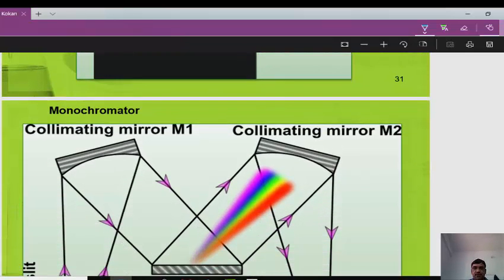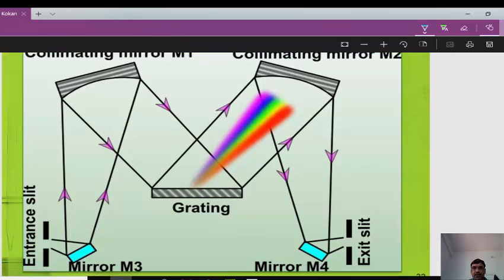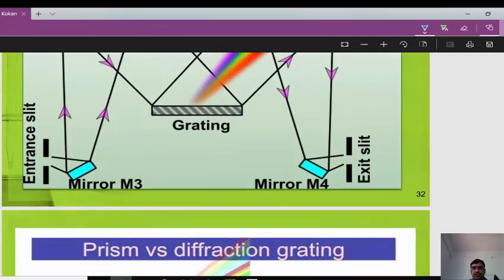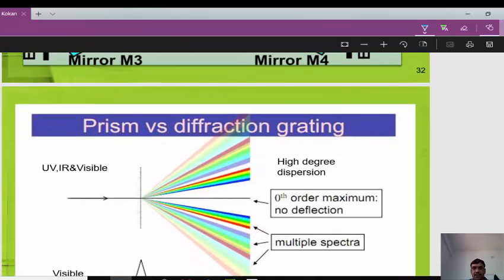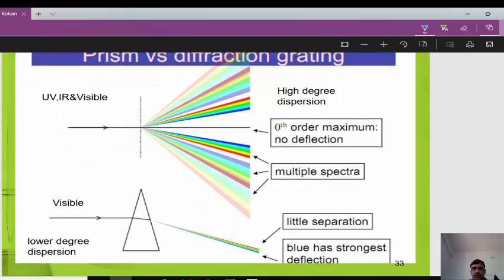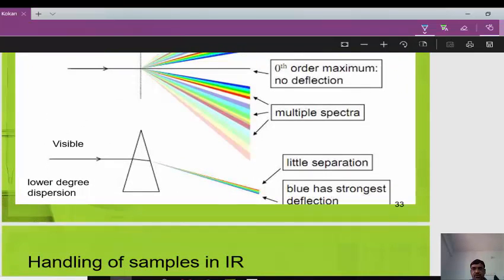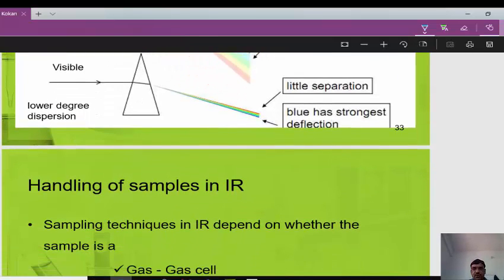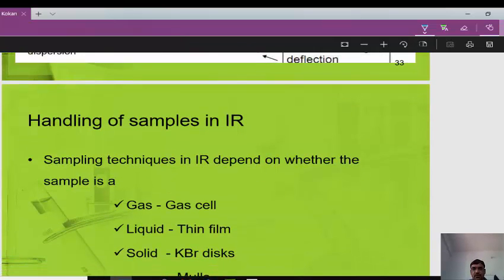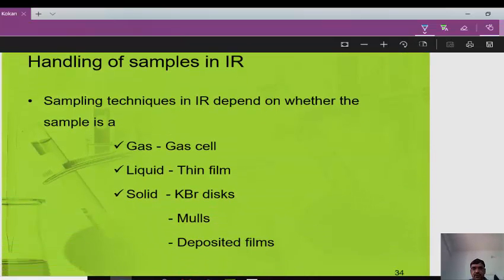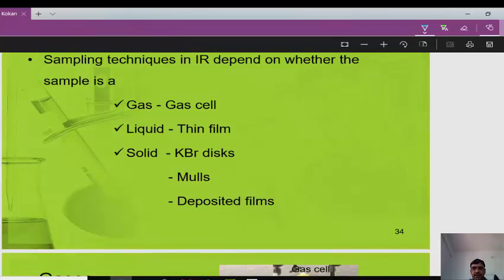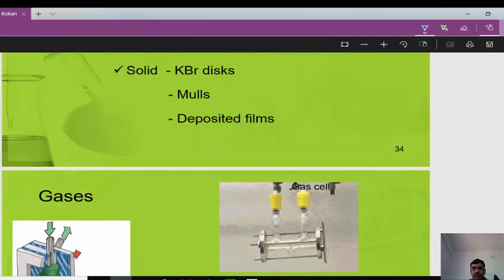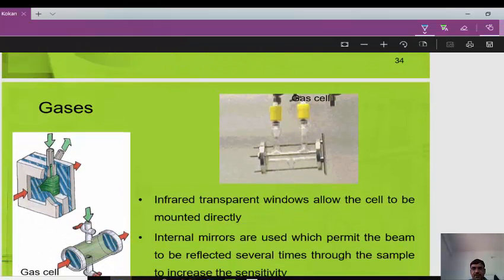A diffraction grating is a device consisting of a series of parallel, closely spaced grooves ruled on glass or reflective surfaces. The grating produces diffraction orders: order 0 (no deflection), order 1, order 2, order 3, visible via collimating mirrors M1 and M2, with an entrance slit. Compared to prisms, gratings offer a higher degree of dispersion across UV, visible, and IR regions, though they produce multiple spectral orders.